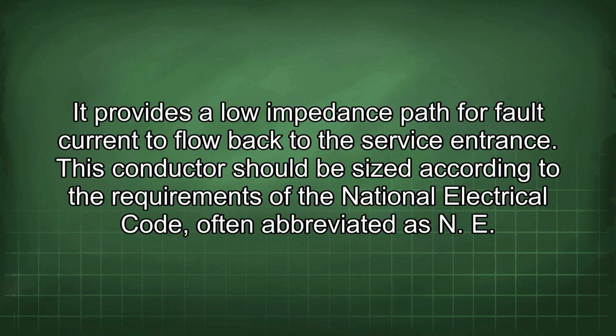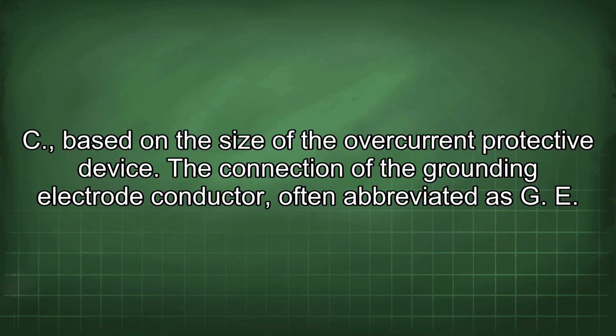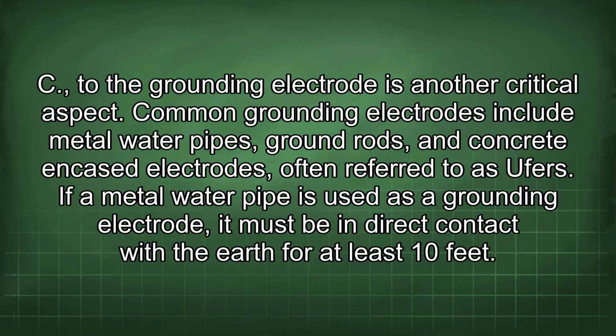It provides a low impedance path for fault current to flow back to the service entrance. This conductor should be sized according to the requirements of the National Electrical Code, often abbreviated as NEC, based on the size of the overcurrent protective device. The connection of the grounding electrode conductor, often abbreviated as GEC, to the grounding electrode is another critical aspect. Common grounding electrodes include metal water pipes, ground rods, and concrete encased electrodes, often referred to as UFERs.